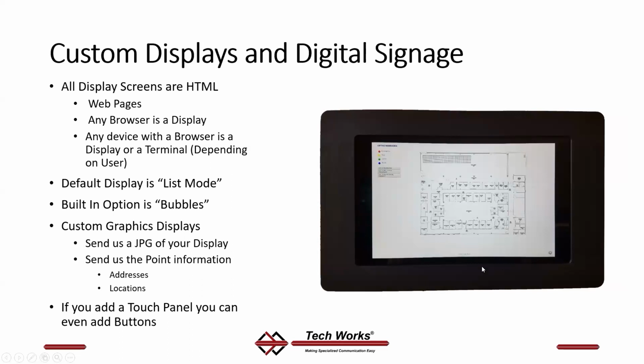If you use a touch panel like a tablet, you can add buttons. There's several different things you can do, but this would be like selecting between different floor plan views. You could click on this one and you'd get one floor plan. They'd click on that one and see a different floor plan. Who might want this? This would be maybe a nurse manager that's over all of the departments and needs to see different things at different times. If I'm only concerned about these few rooms over here in this corner, I would not have these buttons because I don't need to flip between different floor plans.